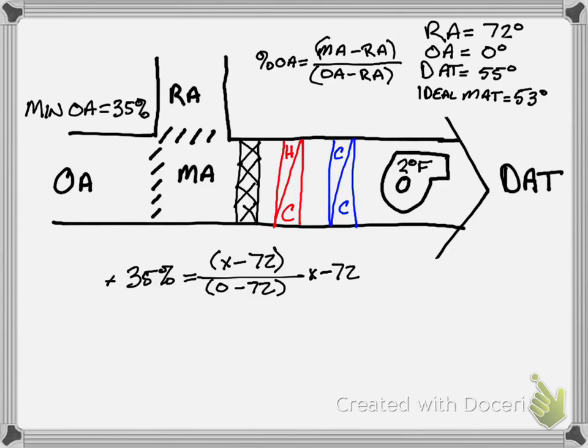So that equals negative 72. We're going to multiply both sides by negative 72. So that's 0.35 times negative 72. And so this comes out to be negative 25.2 equals X minus 72. We add 72 to both sides. And then we come up with X or MAT equals 46.8 degrees Fahrenheit.